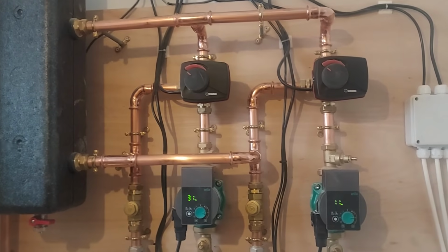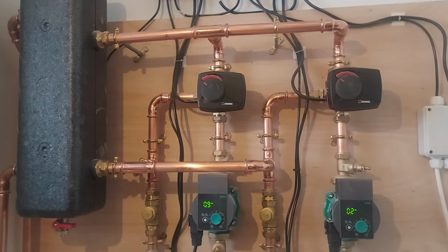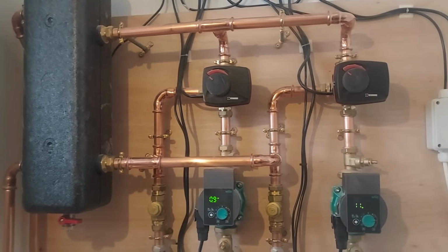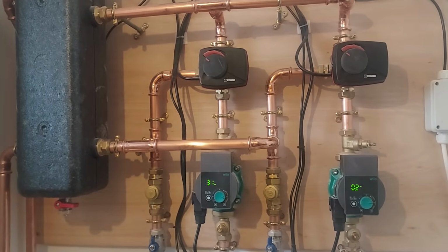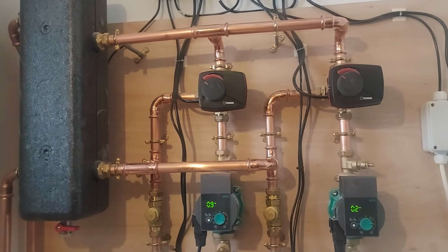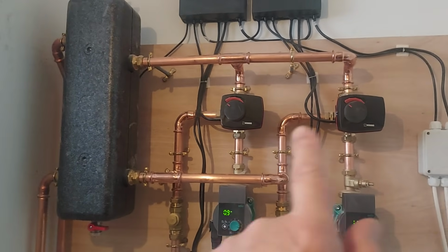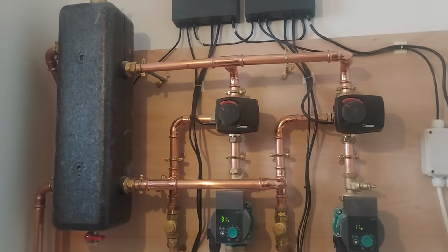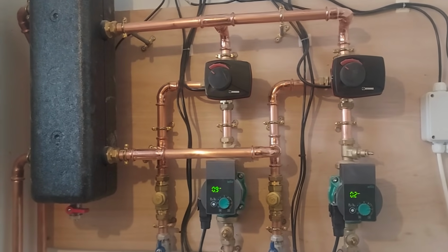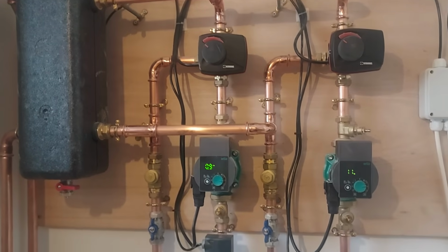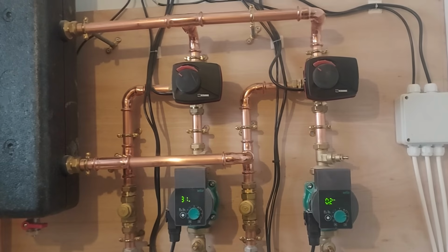It would only make sense if these valves didn't close. So if you had those open but pump off, then you could get some reverse circulation going. But that doesn't happen. These valves close when the pumps go off. So if they're closed and the pump is off, they've already sealed that circuit. So I guess the only other justification for them is if you think you might have poor quality valves which allow some seepage, but these are tight enough to hold a vacuum. So maybe they shouldn't be. Maybe that's the problem. Maybe the valves are too good.